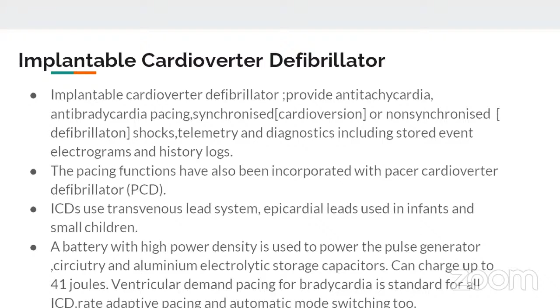Now the modern pacemaker comes with rate adaptive pacing and automatic mode switching. They usually measure the cardiac RR interval and categorize the rate, depending on which the internal computer will decide and deliver the response based on its programmed algorithm. If shock is chosen, the internal capacitor is charged, which takes 5 to 13 seconds depending on the energy to deliver and the age of the device.